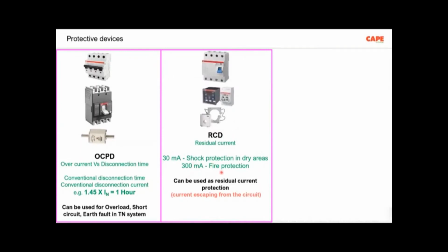300 milliampere is calculated as the requirement. Lesser than 300 milliampere is for fire protection. So there are two things: 30 milliampere shock protection and 300 milliampere fire protection. Of course, for the 300 milliampere fire protection, we must understand that this is based on a 230 volt line. If the operating voltage is a little bit higher, there is still a subject of debate going on.